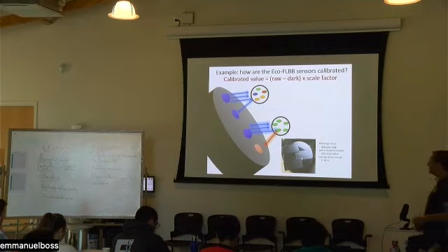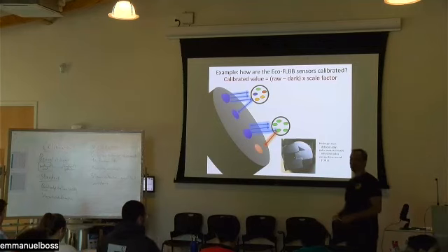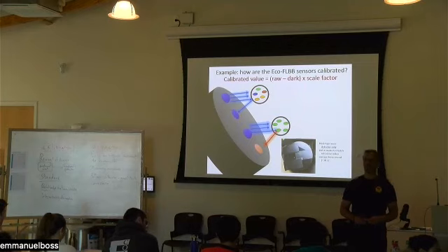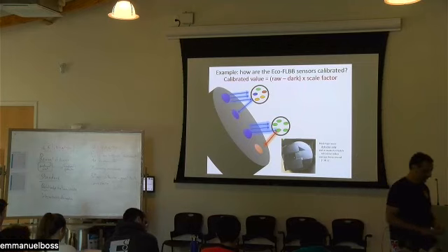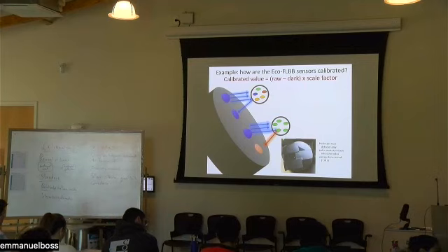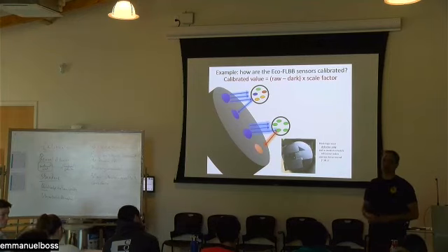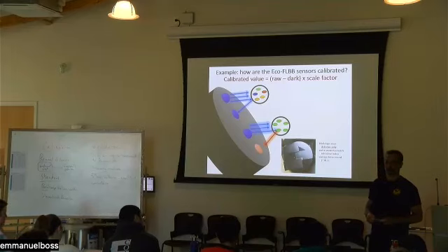But some of the other things you can find out by not putting it in water is sometimes there are electrical instabilities of your sensor. You put that in salt water, and it's a completely different reading than when it's in air. So I agree, it should be in water. But I'm just not convinced about changes in refractive index of the optical glass when it is not in contact with the water when you put tape on it.